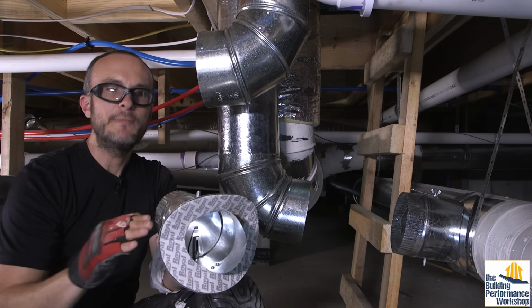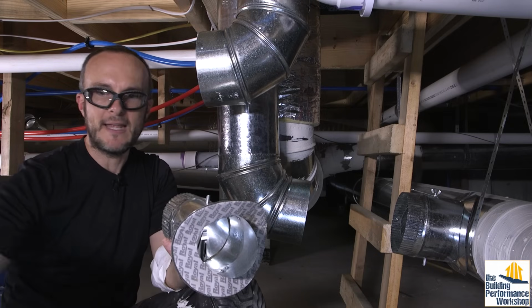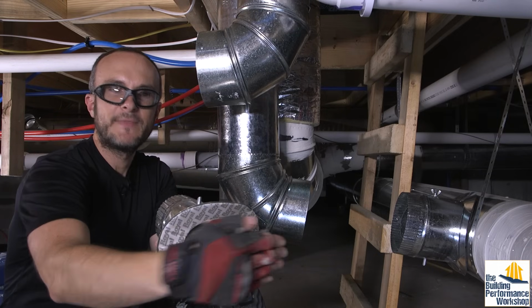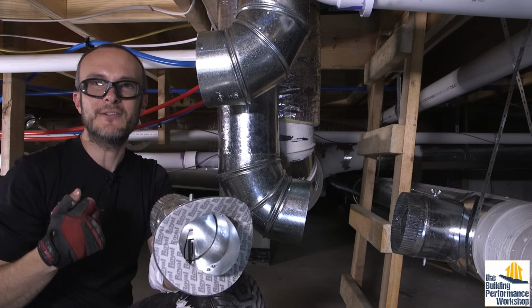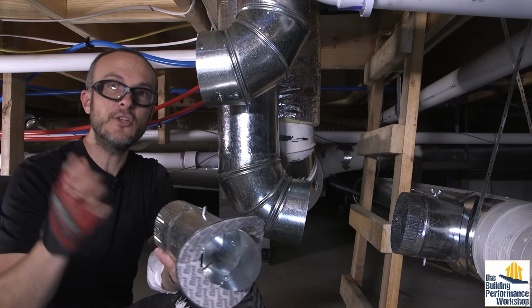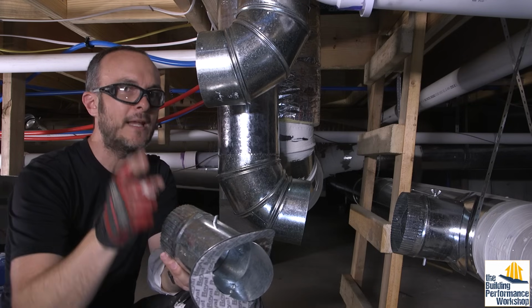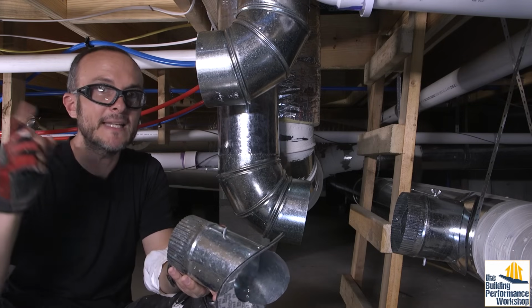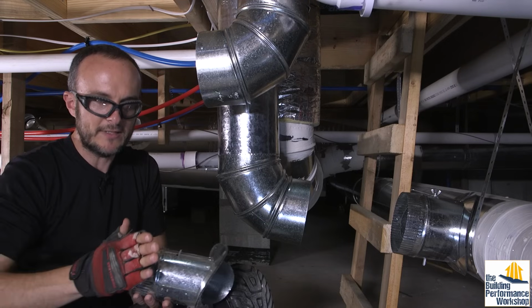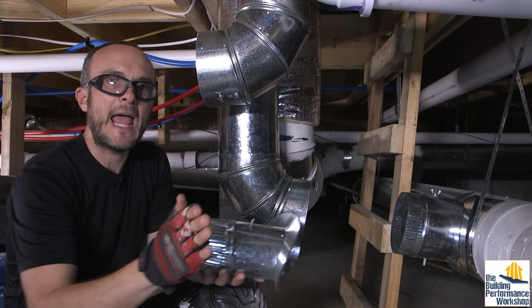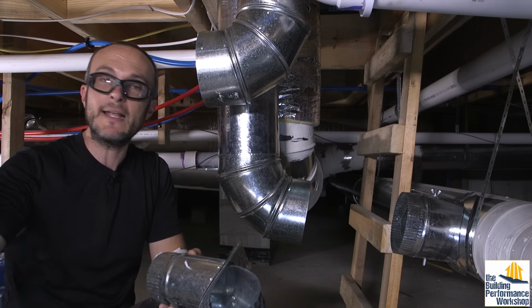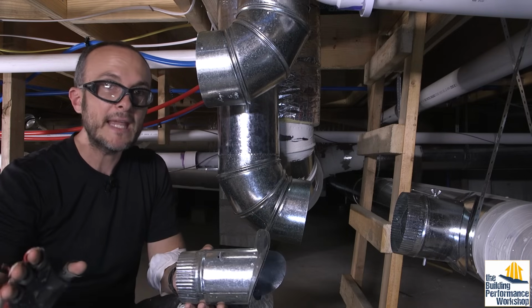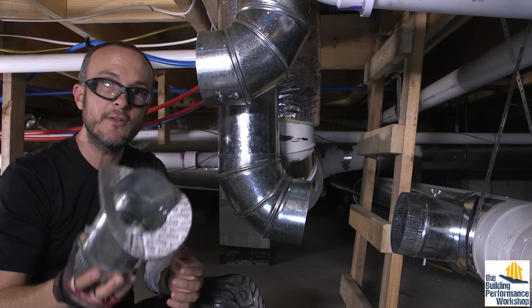If I didn't have that scoop in there, what are the chances that air that's moving in this direction is going to want to take a 90-degree turn in the middle of what it's doing? Probably not a lot. So you can use a 45-degree takeoff, in which case you have to be thinking about space again, because making a ductwork that does a 45-degree branch and then has the time to go somewhere else also takes time. So if you've got a wide open attic, you've got a wide open crawl space, that can be done. You need to think ahead about that stuff. Or you can use scoops.